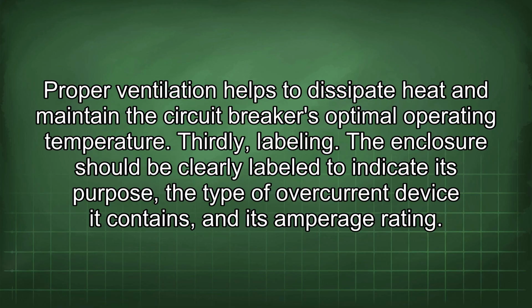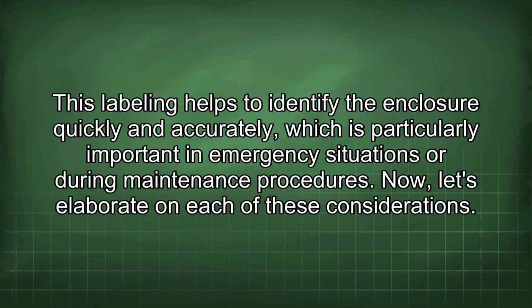Thirdly, labeling. The enclosure should be clearly labeled to indicate its purpose, the type of overcurrent device it contains, and its amperage rating. This labeling helps to identify the enclosure quickly and accurately, which is particularly important in emergency situations or during maintenance procedures. Now, let's elaborate on each of these considerations.